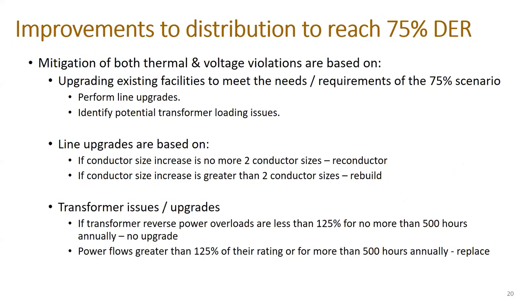When we started doing the analysis, we looked at principally thermal and voltage violations. We didn't look at stability. Distribution stability is not really the same issue as Matthew just defined. There are things like flicker voltage and things along those lines. We didn't go that far down into those issues. We looked strictly at ampacity and meeting the voltage criteria of PREPA.